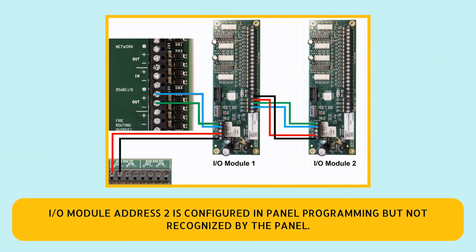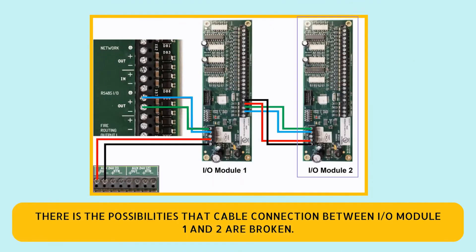I.O. module address 2 is configured in the panel programming but is not recognized by the panel. There is a possibility that the cable connection between I.O. module 1 and 2 is broken.